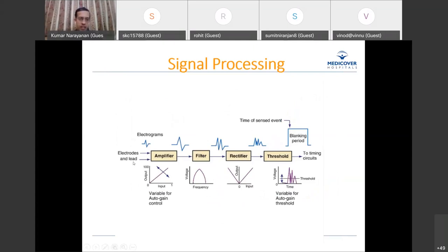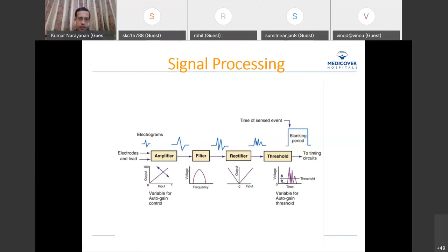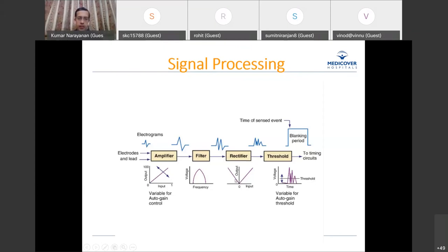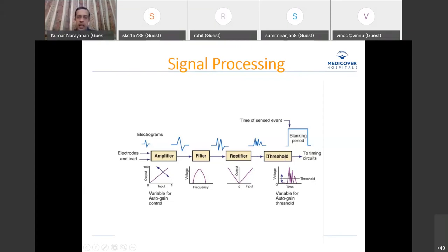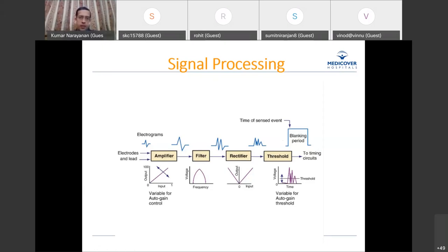To summarize signal processing: the electrodes send electrograms from inside the heart to an amplifier in the pacemaker, which makes the signal large enough to analyze. A filter removes unwanted frequencies. A rectifier takes both positive and negative components and produces a net amplitude. If this amplitude meets the sensing threshold, a sensed event is registered and sent to timing circuits to decide the pacemaker's next action.